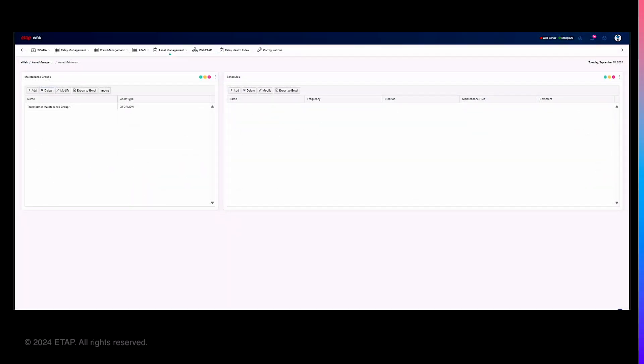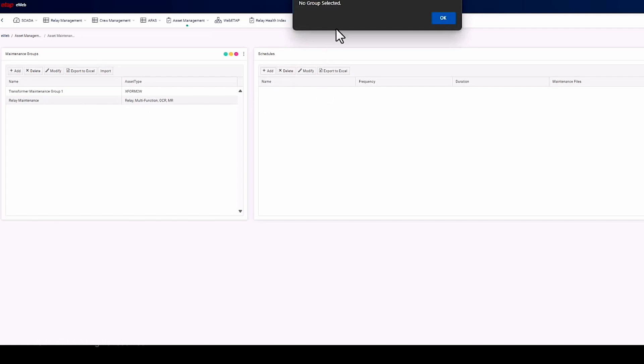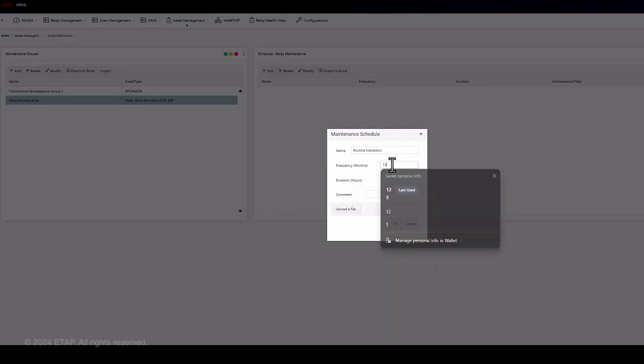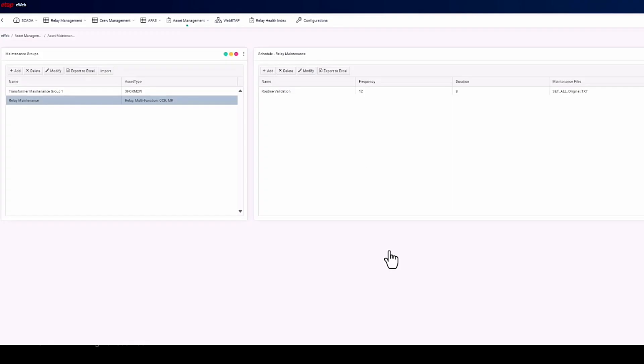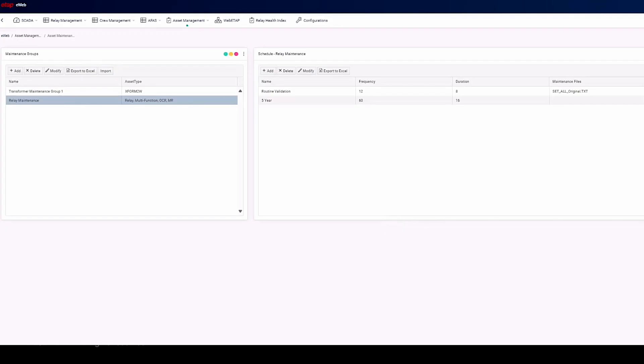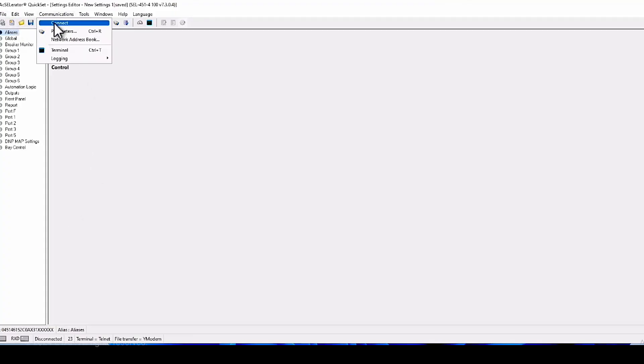Next, I'd like to delve into the relay settings validation process. Our journey begins with the creation of maintenance schedules for the relays, allowing us to track changes and ensure smooth operation. Utilizing maintenance groups, users can establish periodic scheduled maintenance routines for a group of relays, incorporating necessary documentation, procedures, and key individuals responsible for overseeing the maintenance. Upon scheduling, a notification is dispatched to the assigned technician. The first step of relay settings validation involves downloading the settings from the relay using the vendor-provided OEM software, accomplished through the local network or directly at the relay, depending on the IT infrastructure in place.